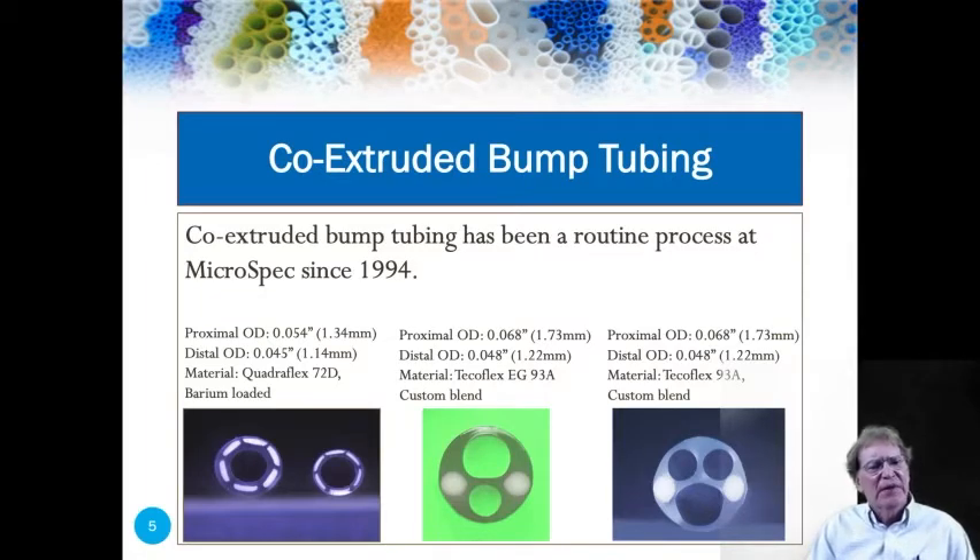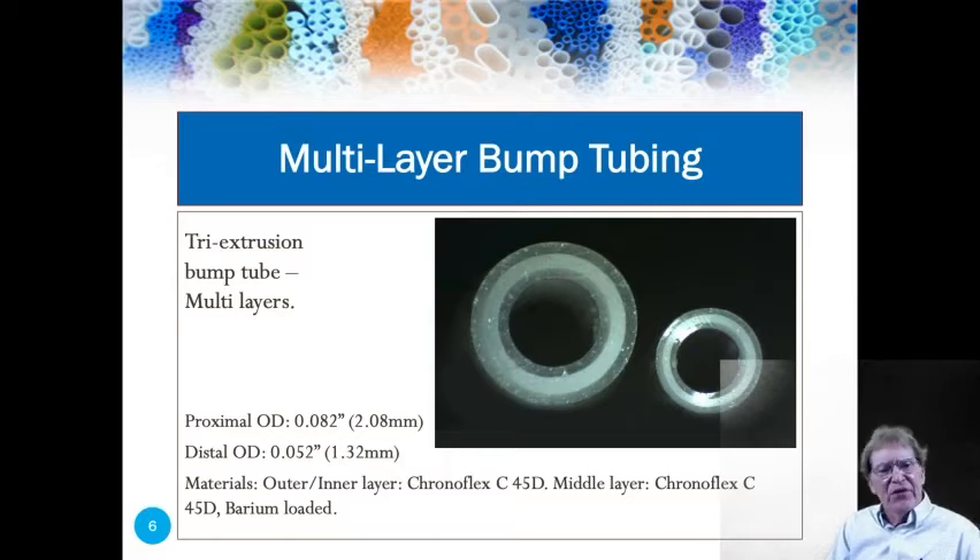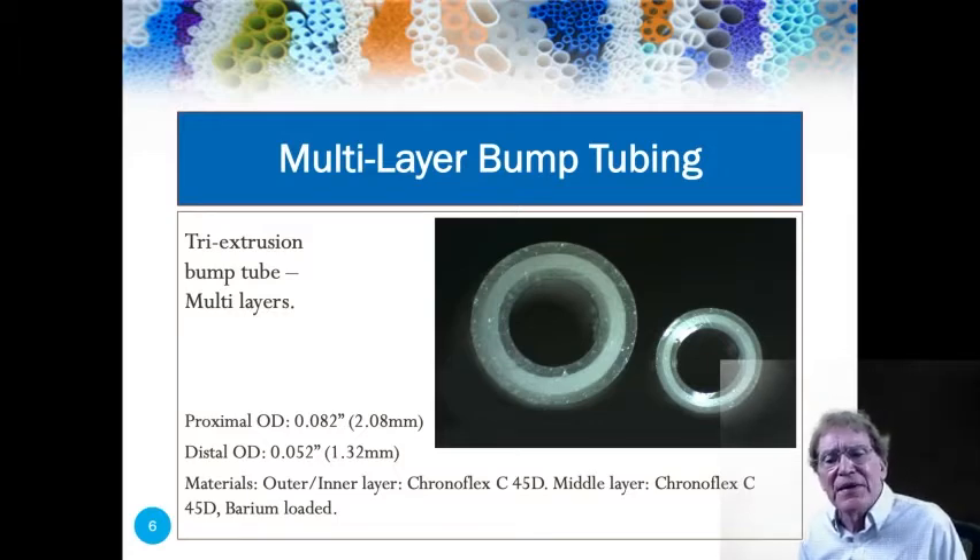Next, we started experimenting with co-extruded bump tubing. You're looking at three tubes here. We have a six-stripe tube, what we refer to at Microspec as a 2x2 — two lumens and two radiopaque stripes — and a three-lumen with two stripes. Here we've incorporated another extrusion technology: tri-extrusion. We have an ABA layer — Chronoflex — two Chronoflex layers with a fully radiopaque middle layer.